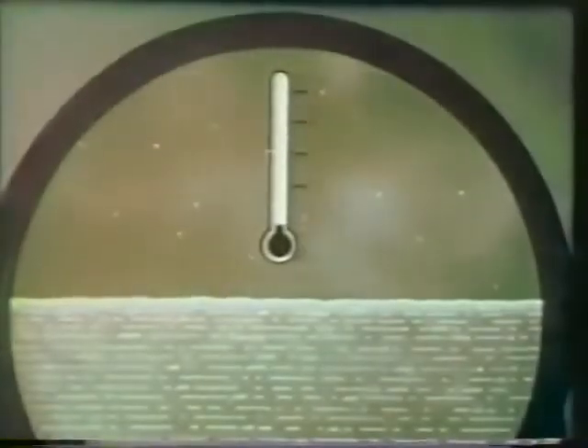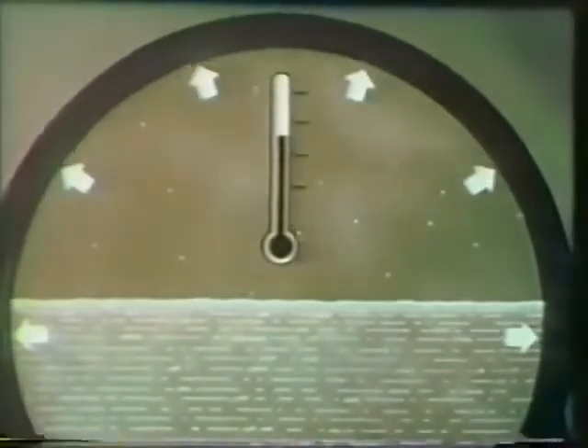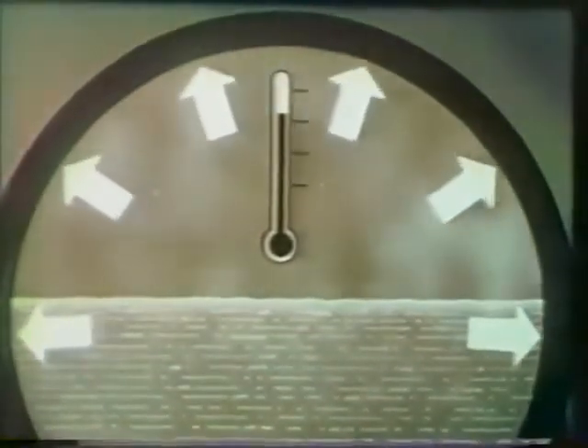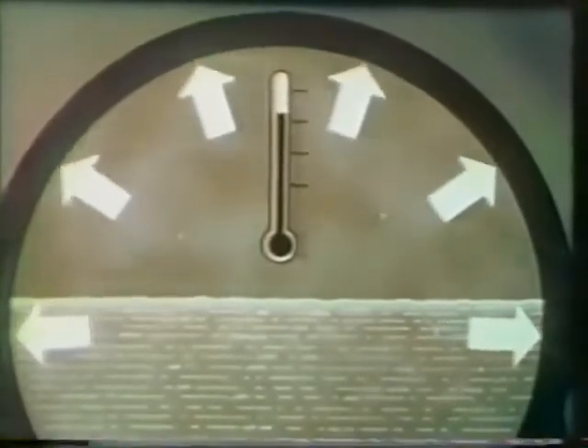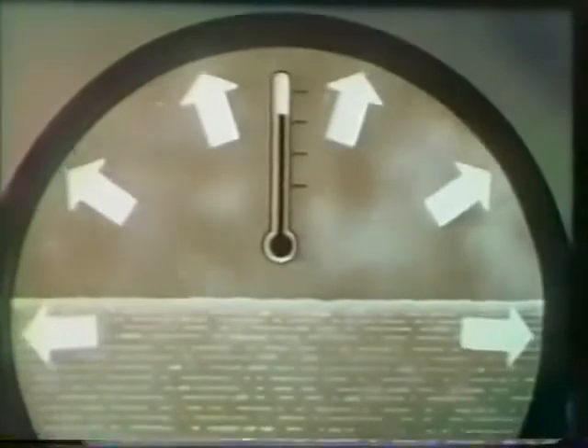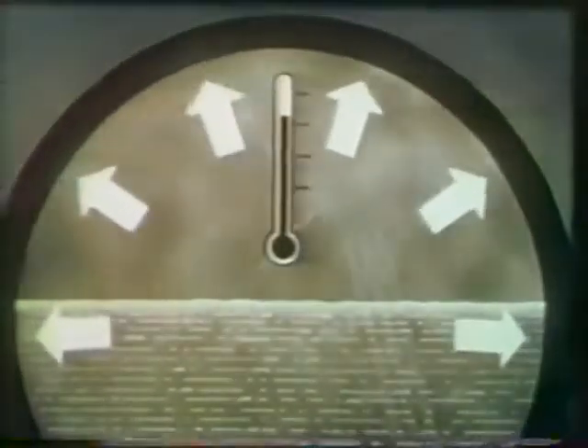The hotter steam is, the better it does its work in the ship's main propulsion turbines. In the steam drum, the saturated steam is in contact with the boiler water. As long as steam is in contact with water, any increase in the temperature of the steam can only be obtained by an increase in pressure. Thus, it is not practical to bring steam to the maximum desired temperature in the steam drum because of the tremendous pressure that would be encountered.